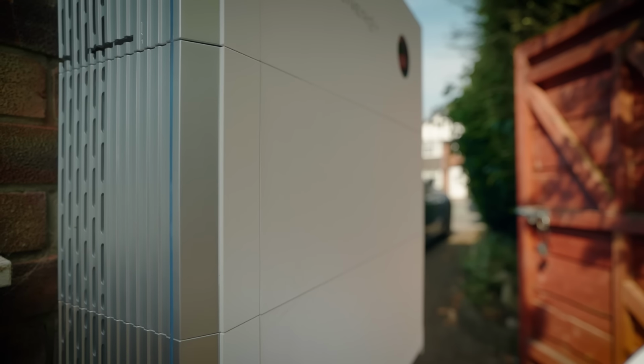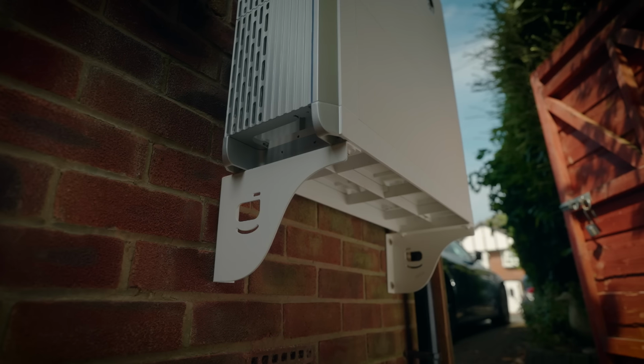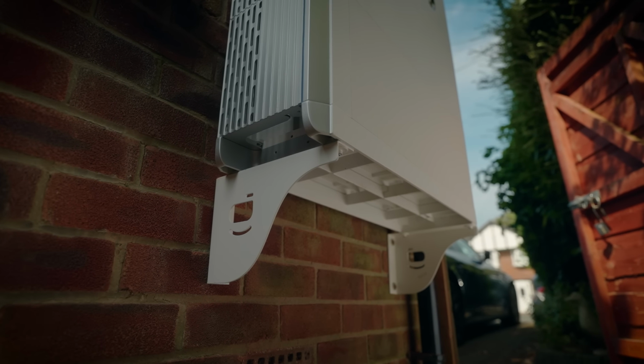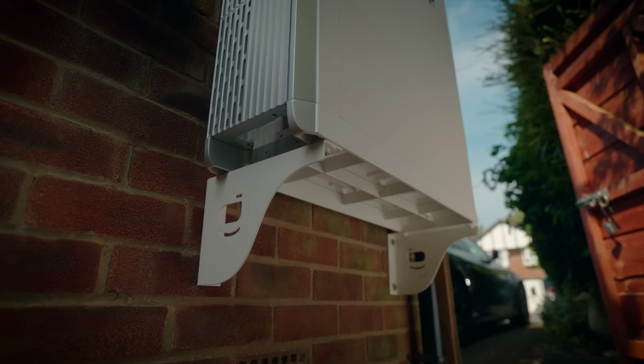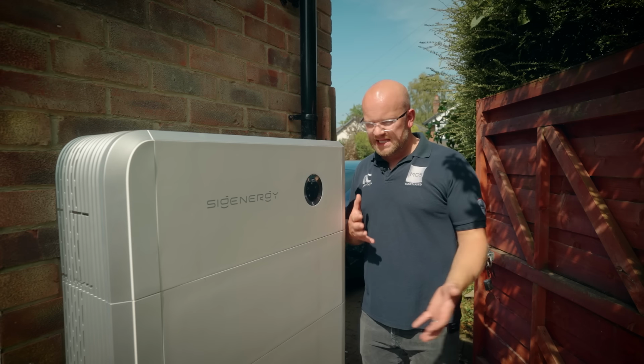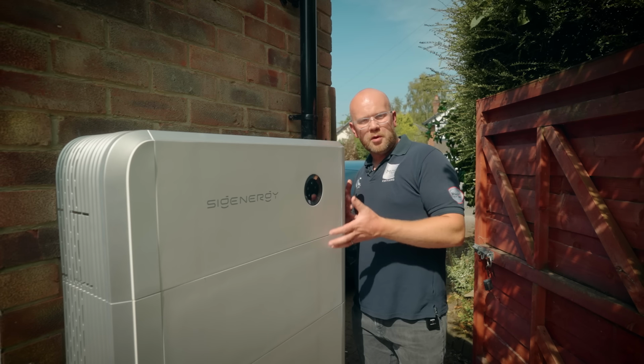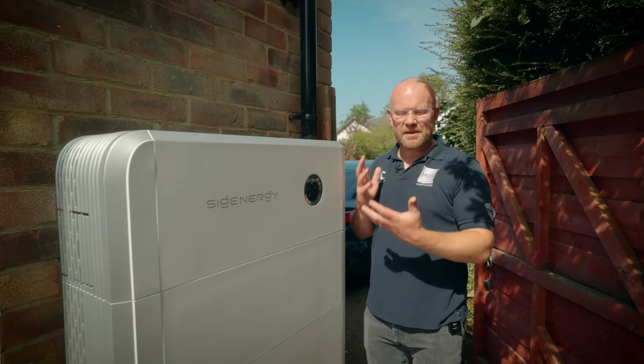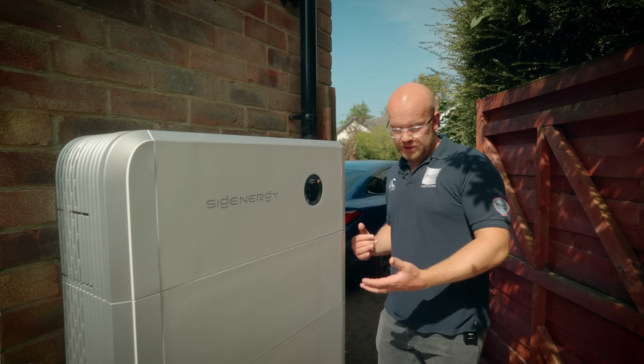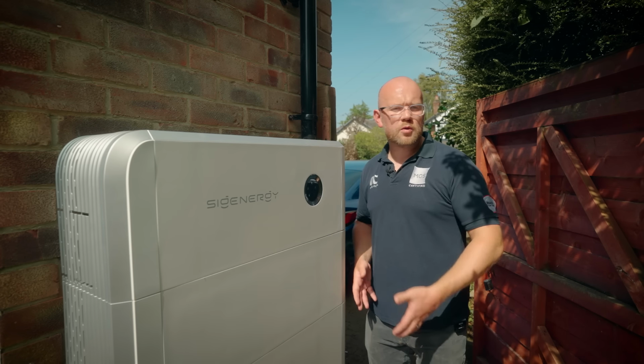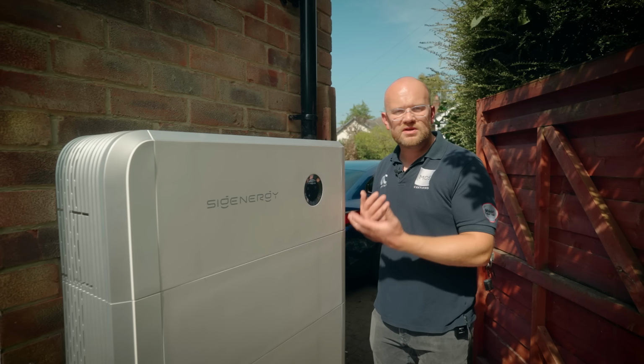One of the things you'll notice with this installation versus the office is that when we have 2 battery modules, we can do them wall hung. When we go more than 2 modules, they have to be a floor mounted kit because of the weight of them. This client wanted this because it's neat, tidy, it's sat out the way, we can pop it to one side. Now, if the client decided at a later stage, I could really do with a bit more battery storage, can't imagine that's going to be the case here, then all we do is take the wall mounted bracket off, put in a floor mounted system, and then we just refit the inverter.